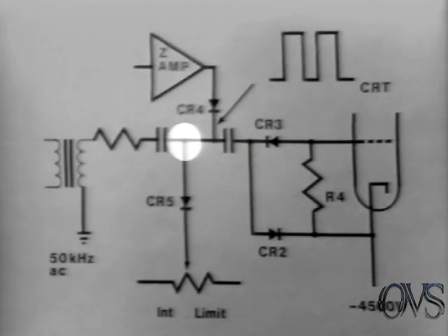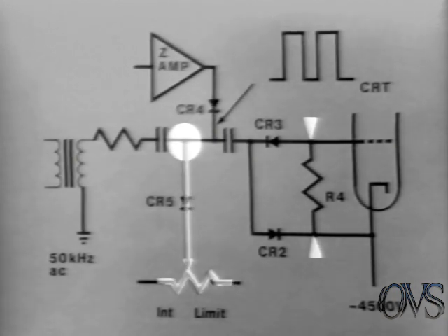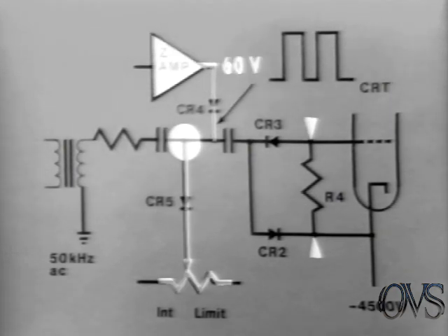Therefore, the voltage drop across R4 will be a function of the difference in voltages between the intensity limit pot and the output of the Z-axis amplifier. For example, if the Z-axis amplifier output is at 60 volts and the intensity limit pot is set for 100 volts, then the voltage excursion at this junction will be 40 volts.